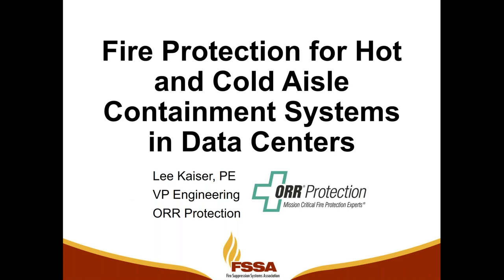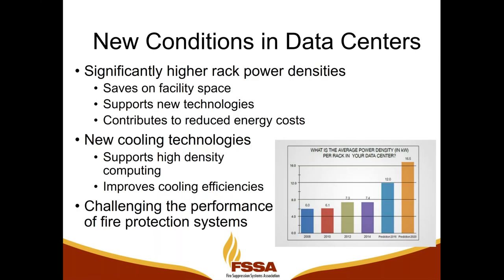As we discussed, we're going to talk about data center fire protection with regards to hot and cold aisle containment systems. And so why this is important is because data centers are a fairly large user of many of the gaseous fire suppression systems that the Fire Suppression Systems Association represents. And two things really kind of rule the data center space, and that's power to the computer servers and IT hardware as part of that, and the cooling, the HVAC cooling that's required to cool those down. A lot of the things we do in a data center is to deliver power and cooling properly so the IT function in a data center can be handled.